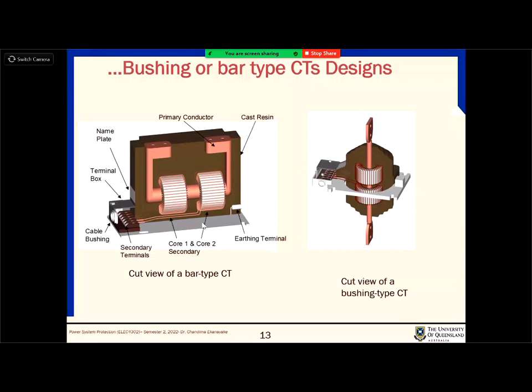Yeah, so one is to improve the security. You will have two things now. If one fails, the other one works. And the other thing is to compare things. As an example, what happens if one wire is broken? You need to have some sort of comparison in the circuit to identify whether there is a local fault or not. As an example, if suddenly in one measurement system the current drops or something, the first thing you do is not to go and switch off the circuit breaker. You need to compare it with the other one and see that the other one still hasn't changed. So the most possible cause of that sort of error is the circuit associated with that, so that you don't operate the system for unnecessary reasons.